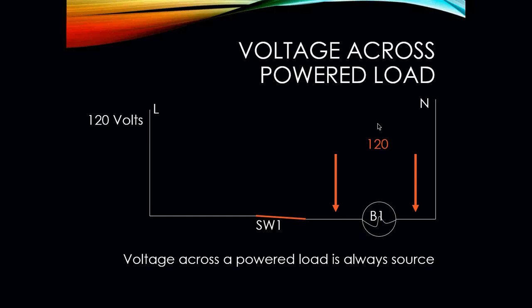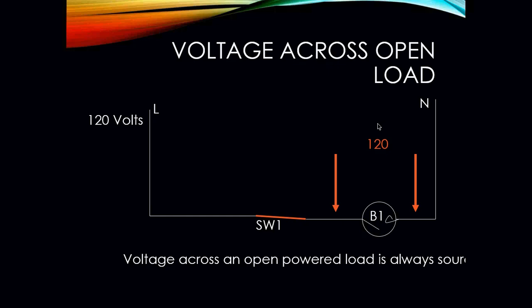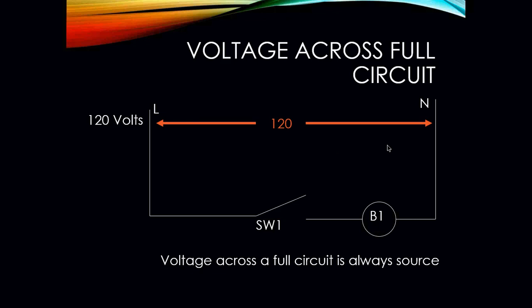Voltage across the powered load, I'm always going to read source voltage. Why? Because the load is my power consuming device. So my load and my meter will pick up that difference in potential. So in this case, I'm reading 120 volts. And if I have a bad load or an open load, and that load is no longer working, I'm also going to read a source voltage, because my load is now acting like an open switch. Okay, so power has made it all the way through my switch up to this point, but since it can no longer travel across to the other side of my load, I am now going to read my source voltage. When you are measuring across an entire circuit, you're going to read source voltage as well, because it is a complete path. It is a source of power.